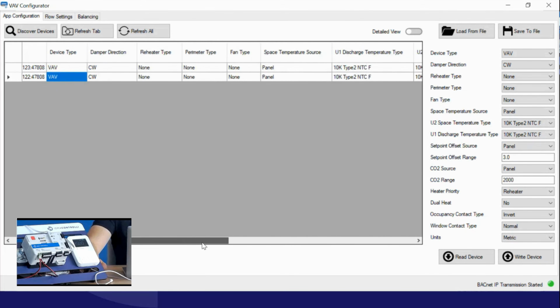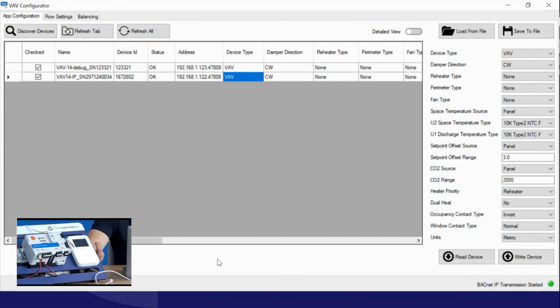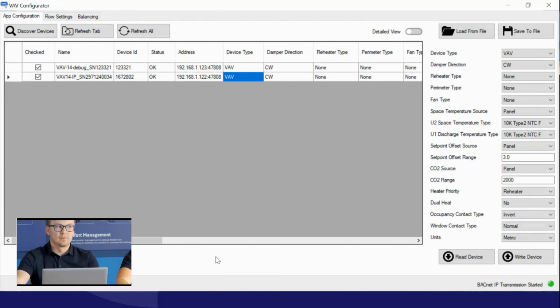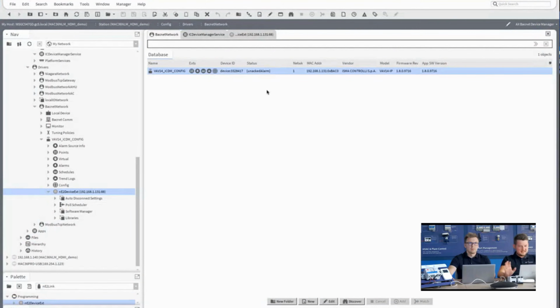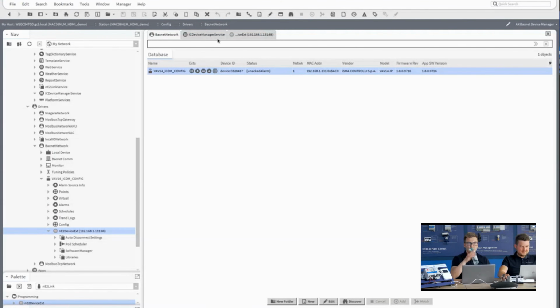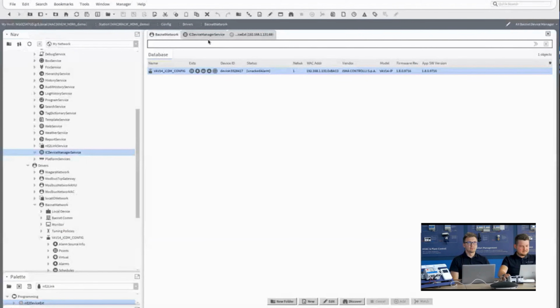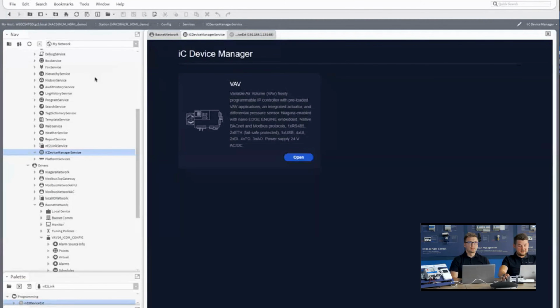Yeah. So one-to-one, one-to-many, we got this in the iSMA Configurator. And by the way, let me now share the screen, and I will tell you, we have the same feature set directly in Niagara. You can all see it. I have one VAV14 IP added into my BACnet network. Once adding the VAV unit to your BACnet network is done, you can open our IC device manager service. It's right here in my services. We have a nicely done menu. Right now it's just for the VAV, but we'll expand it for more devices in the future to allow seamless configuration of them.